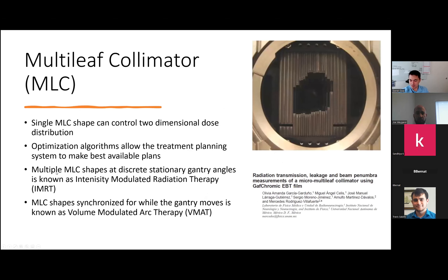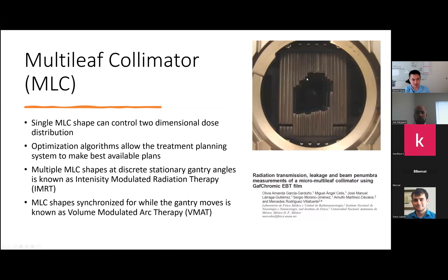A little more detail on the MLC, or multi-leaf collimator. If you look in the gantry you'll see thick tungsten leaves, eight to ten centimeters deep. The outer ones are one centimeter wide and the inner ones are five millimeters. For radiosurgery machines you can have two-and-a-half millimeter internal leaves and one centimeter external leaves. With the MLC you have the benefit of shaping your dose two-dimensionally, and if you deliver this at different gantry angles you end up shaping the dose three-dimensionally.